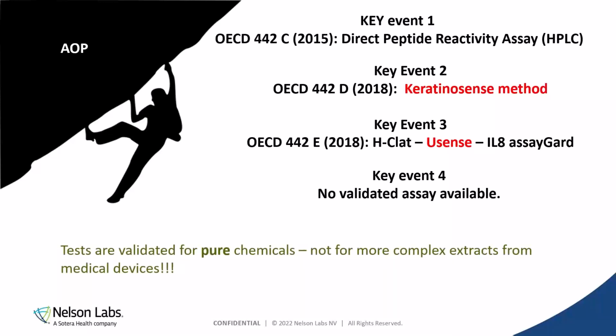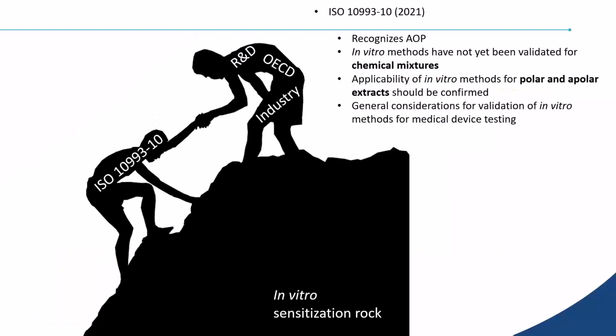So again, very important to understand. These tests are currently only validated for pure chemicals and not for more complex extracts from medical devices. Because to test medical devices, you need to prepare extracts. You need to prepare extracts in an apolar medium. You need to prepare extracts in a polar medium, and of course, it's never a single chemical that leaches out of the medical devices. So you have complex mixtures, and we are not sure that these methods will react the same as they do on a pure chemical.